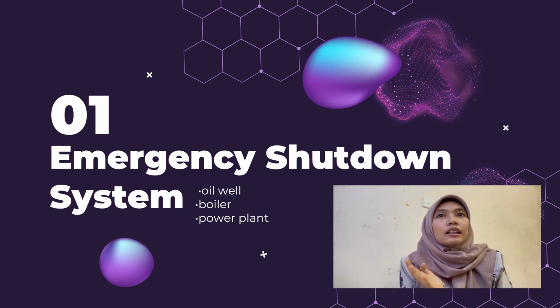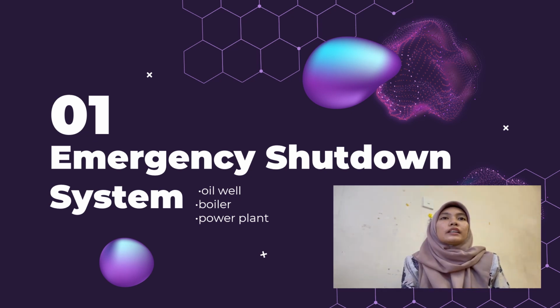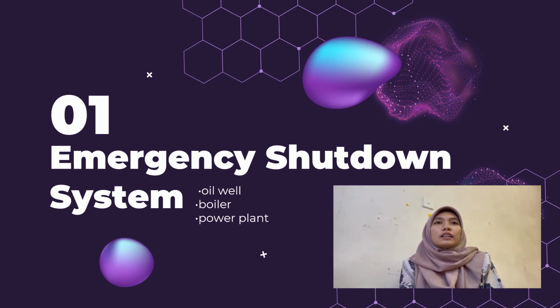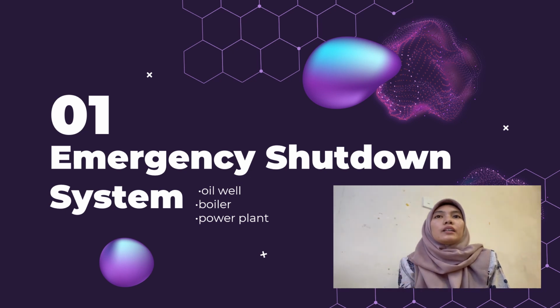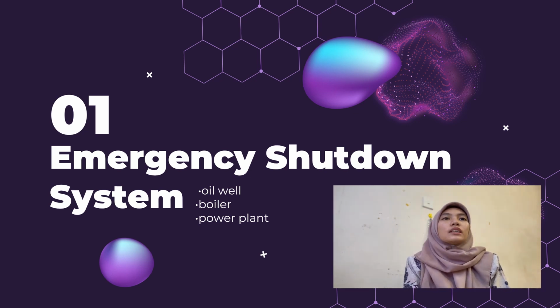Next, the boiler has similarity with an oil well too. The pressure inside the boiler can increase above a safe level and cause the boiler to explode. In this system, both pressure and temperature of the steam can trigger the emergency shutdown system activation when they exceed the preset value. And lastly, in a power plant, emergency shutdown systems are triggered by a few different things. In one application, once the temperature of gas exhaust reaches an unsafe level, an emergency shutdown system will shut down the turbine, producing the exhaust to lower the overall temperature of the system.